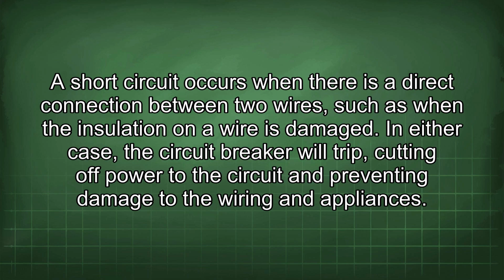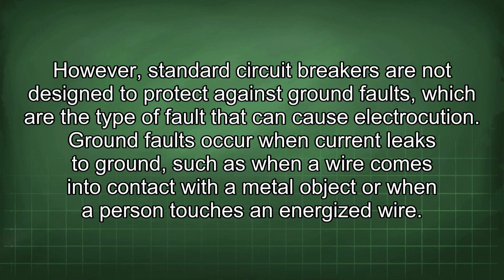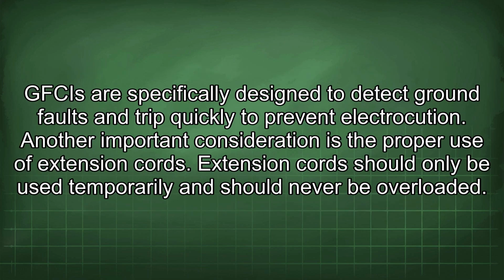and appliances. However, standard circuit breakers are not designed to protect against ground faults, which are the type of fault that can cause electrocution. Ground faults occur when current leaks to ground, such as when a wire comes into contact with a metal object or when a person touches an energized wire. GFCIs are specifically designed to detect ground faults and trip quickly to prevent electrocution.